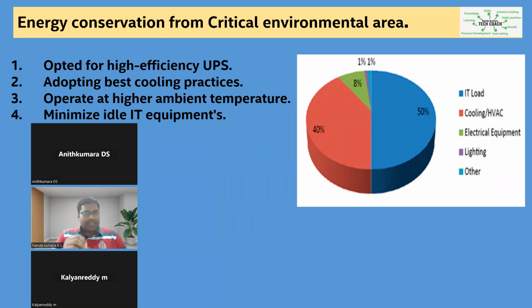If you increase the air temperature by 1 degree, I'll show one slide. You can take any scenario, even a small 1 ton air conditioning unit as well as a 100 kilowatt air conditioning unit. If you set it at 18 degrees, the average consumption per annum, as calculated in a study conducted by an energy research institution, is around 13 kWh per day. If you set it to 24 degrees, the power consumption is 10.5 kWh. If you set it to 27 degrees, power consumption is only 9 units. So this study clearly shows that if you increase the temperature by 1 degree, 3 to 4% of power consumption will be reduced.